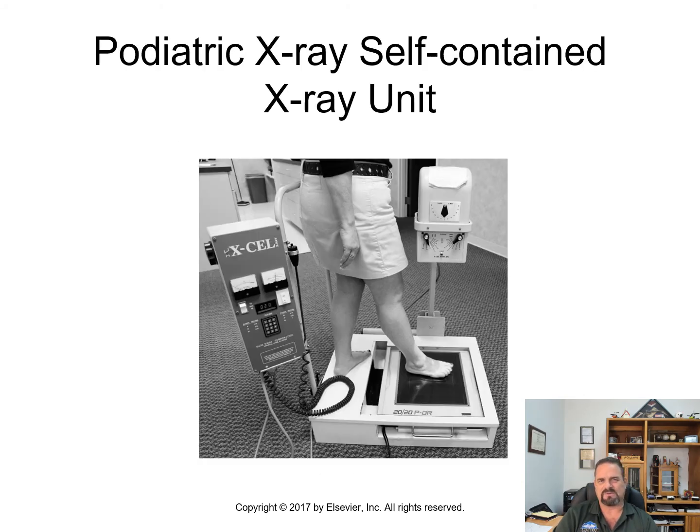All right, so this is a podiatric X-ray self-contained unit. We don't really see these in other places other than the specialty physician's office of podiatry, because it's very specifically made to X-ray the foot and the ankle. It's very, very commonly used in the podiatry world. It is a self-contained X-ray machine. Note the control console behind the patient and the X-ray tube and collimator above the foot.